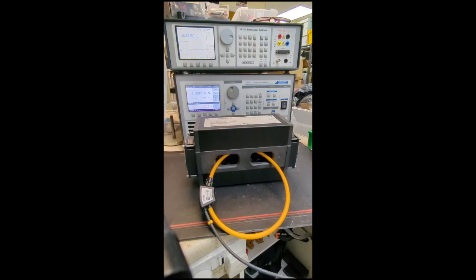Now, what we can do to test this is use the fixture that we have in our test fixture and our calibration station in the development lab. What you see there, the black box, is a 25 turn current test coil. So if you put in 1 amp, it's generating 25 amps essentially. With this particular rig, we can go up to 2,500 and we can go down to fractions of an amp.